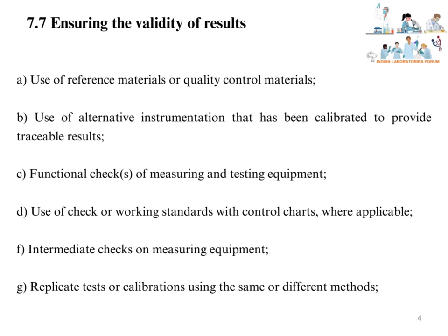Functional checks of measuring and testing equipment, for example, daily verification of balances, daily verification of pH meter, etc. Use of check or working standards with control charts, where applicable. Use of working standards and spiking of working solution into samples and checking the recovery, and use of a statistical quality control chart for detecting trends.